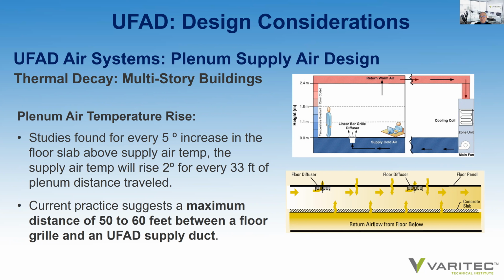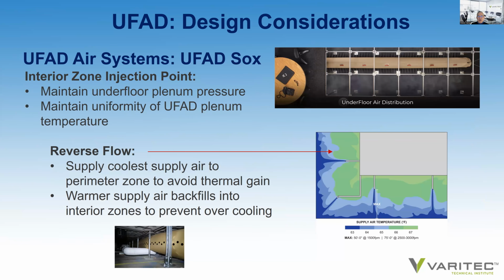So the current practice in laying out underfloor air systems and the injection point of supply air into the plenum is to be at a maximum distance of 50 to 60 feet between the floor grill and the UFAD supply duct. New technologies, however, are now applied that allow for an even more effective dispersion of properly tempered air through diffusers, especially at the perimeter. It was UC Berkeley's Center for the Built Environment, to my understanding, that came up with this understanding called reverse flow, and is adopted by DuctSox in their UFAD SOX design, 10, 13 years ago.